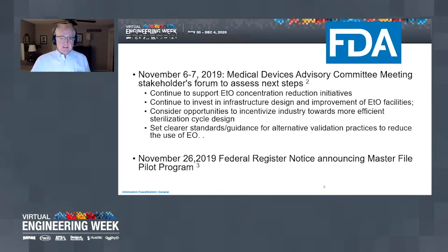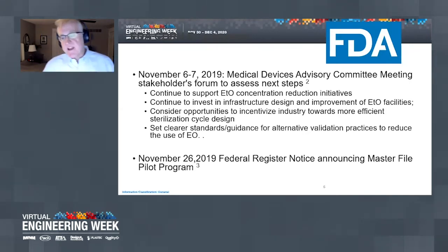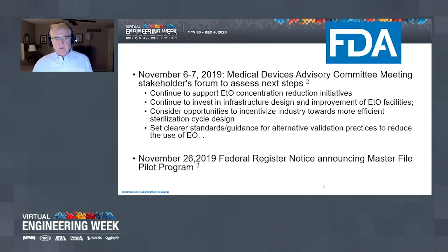So suffice it to say that the bell has been rung, and it's time for all stakeholders to take steps to reduce EO in their sterilization process and develop scalable methods to replace EO, but that's many, many years away. So riding this wave of collaboration, the FDA announced an EO reduction master file pilot program in the Federal Register on November 26th. This presented an alternative regulatory pathway for industry to report changes related to the reduction of EO use for PMA products. Here again, credit goes out to FDA for stepping up and providing new regulatory pathways to incentivize industry and reduce the burden of making the shift to EO reduction.